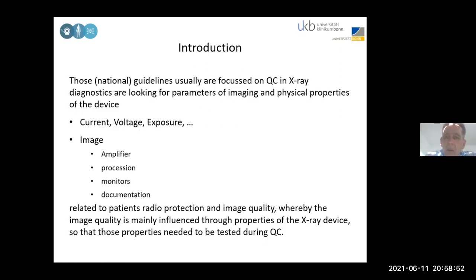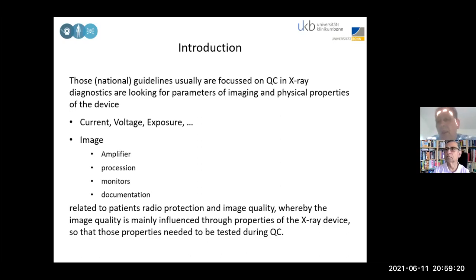So, what are the physical properties of the X-ray device we have to check before we go to the imaging device? The first things are usually current, voltage, exposure, field size, and distances, so geometry. These are the first things we need to set up, so that the machine has the specifications. But in the end, for diagnostics, it is important to see what my image quality is, because on the basis of the image quality, you or your physicians decide whether this is the diagnosis or it isn't.